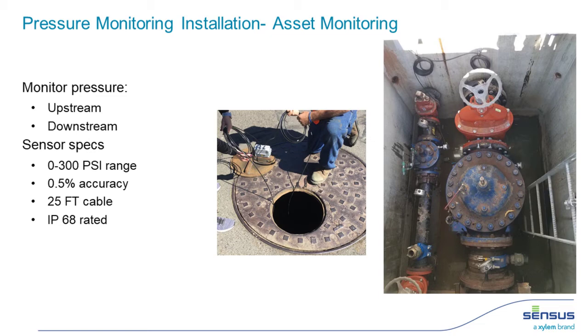Thanks, Adrian. Beyond installing residential water meters with a built-in pressure sensor, we also installed some pressure transducers at our PRV locations—upstream and downstream of the PRV—just to monitor the function of that unit and make sure we were dropping the pressures appropriately. Installation is pretty straightforward; we used existing pressure gauge taps and installed the transducer right into those taps. It only took several minutes to do this.